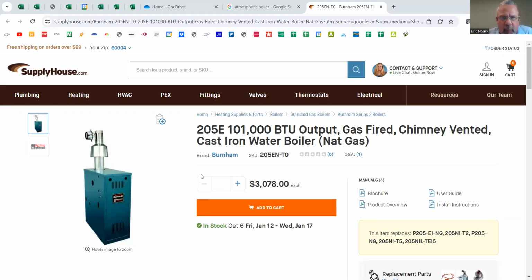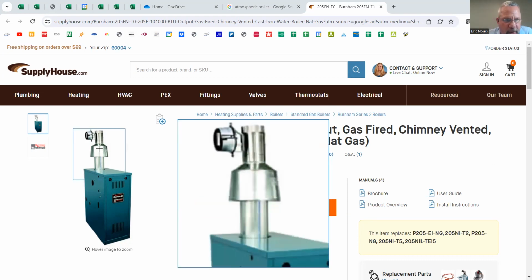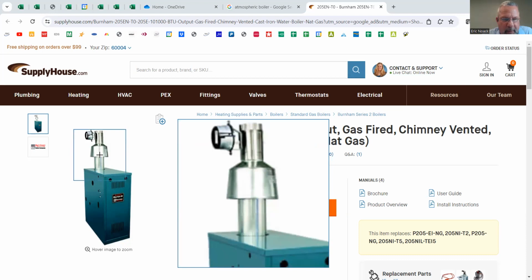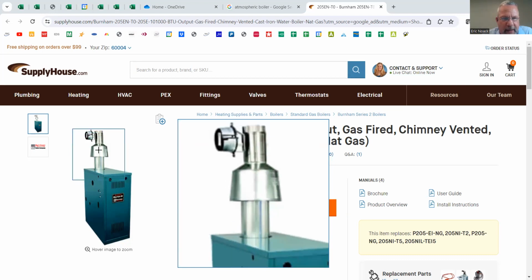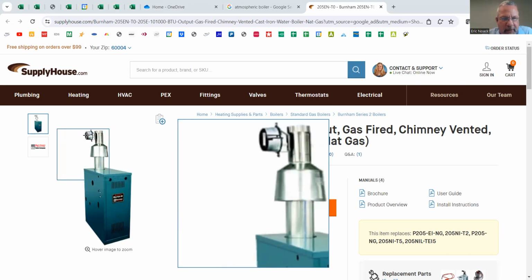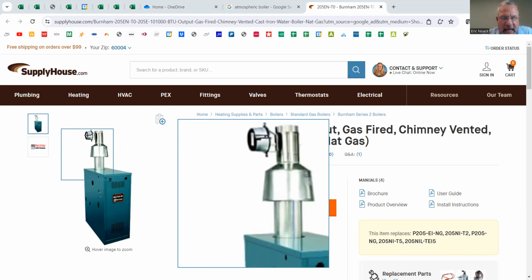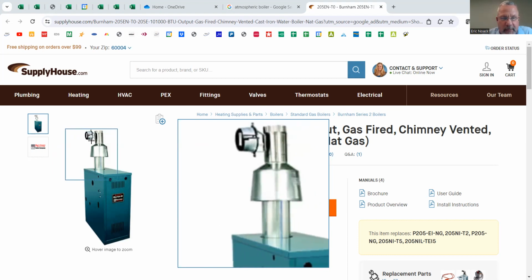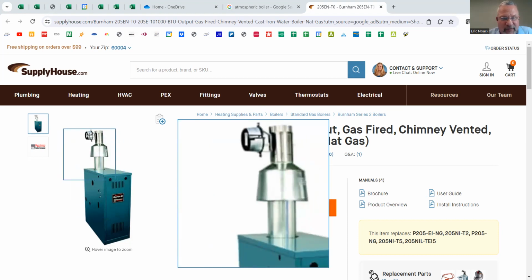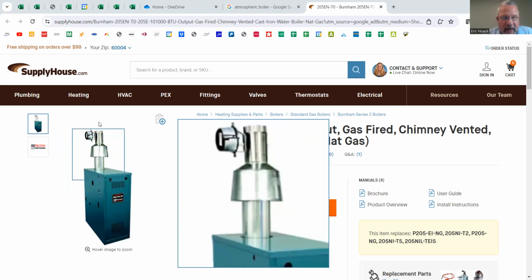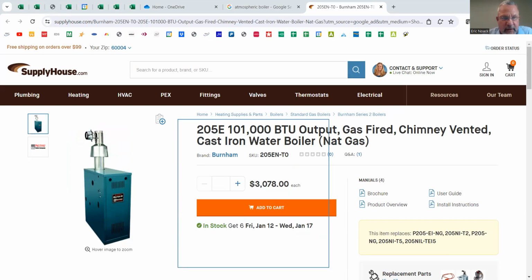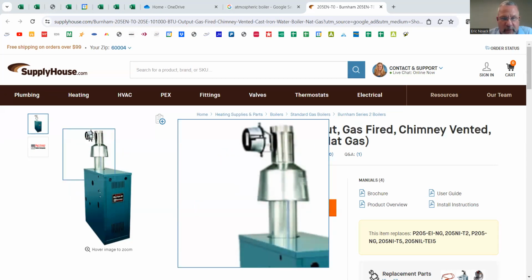So this is a basic gas-fired boiler. This is called an atmospheric damper right here, this upper part. It's open underneath to let air get drawn in. And there is a damper up here that opens and closes every time the boiler stops firing. What this does is help trap some of that heat in there. If that wasn't there, when the boiler stops firing, it would lose a lot of heat out that flue pipe and lose efficiency. So they'll oftentimes put one of these dampers on here. They come with it to get to the efficiency that they need to be.